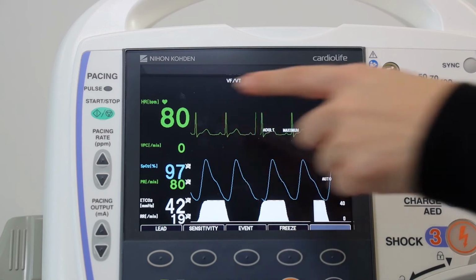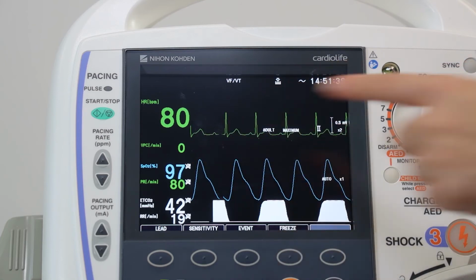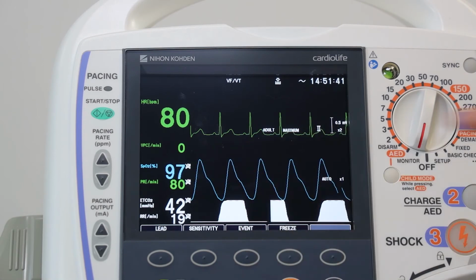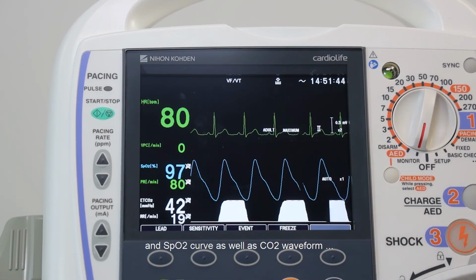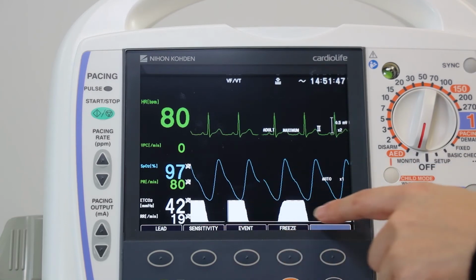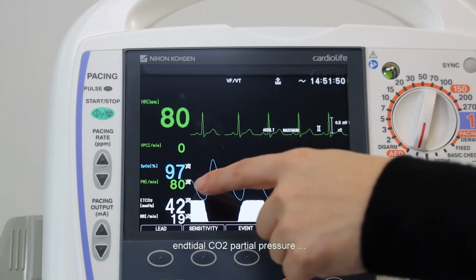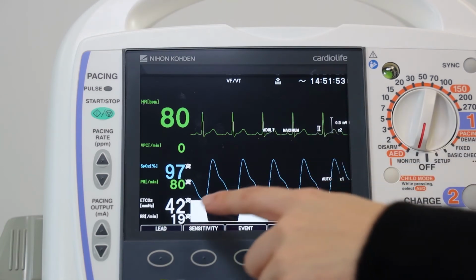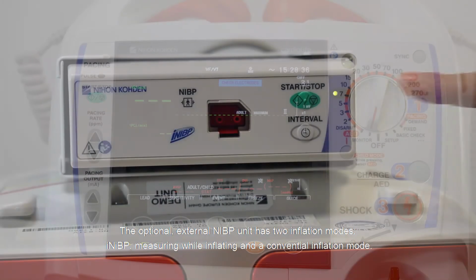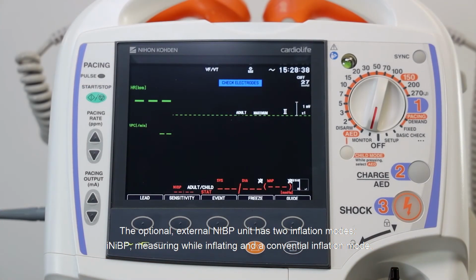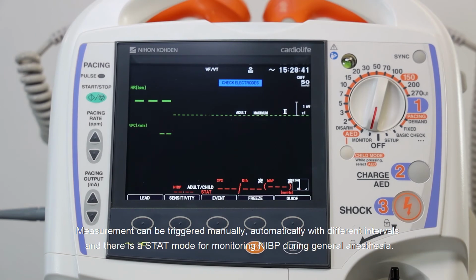heart rate, SpO2 value, pulse rate, and SpO2 curve, as well as CO2 waveform, end-tidal CO2, partial pressure, and respiration rate. The optional external NIBP unit has 2 inflation modes, iNIBP, measuring while inflating, and a conventional inflation mode. Measurement can be triggered manually, automatically with different intervals, and there is a stat mode for monitoring NIBP during general anesthesia.